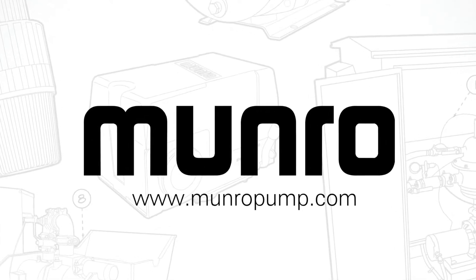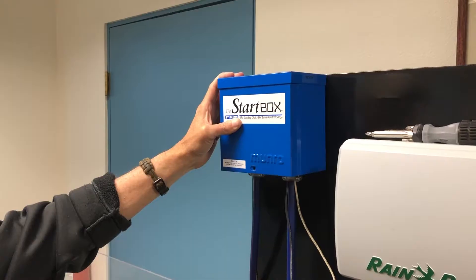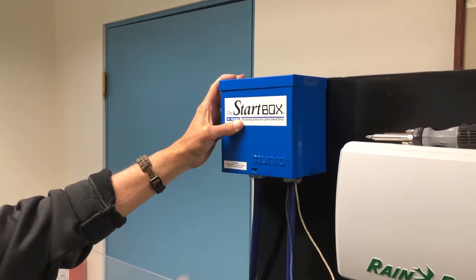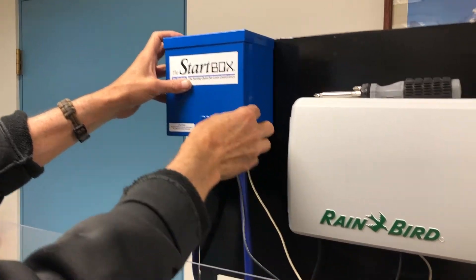Today we'll be demonstrating how to wire a Munro start box. Before you begin this project, be sure that your breaker is turned off. For the purpose of this demonstration, we have already pre-run power wires from the breaker box, wires out of the pump motor, and the master valve circuit into the box.